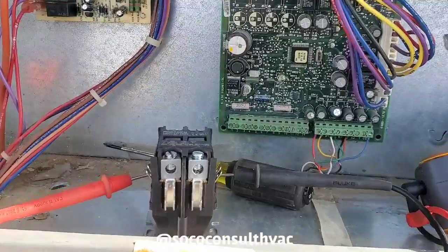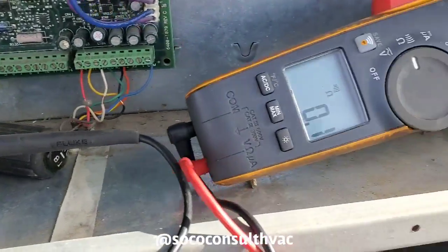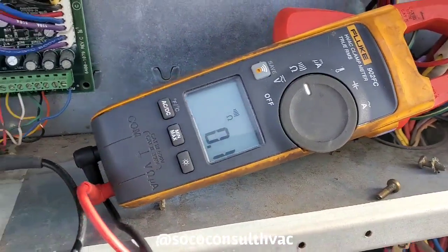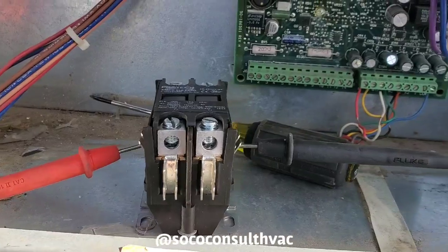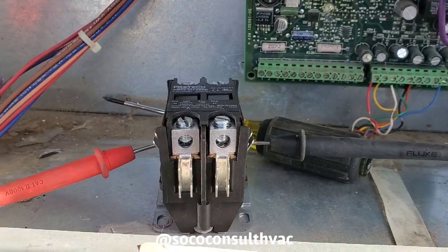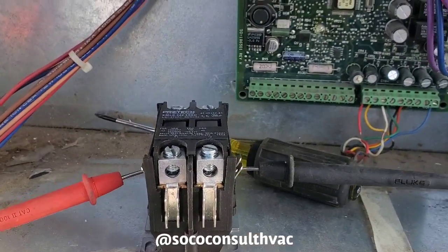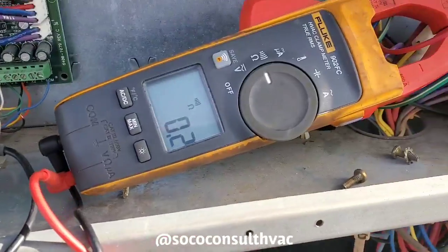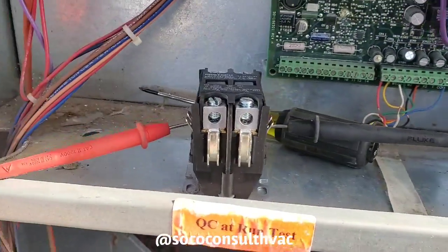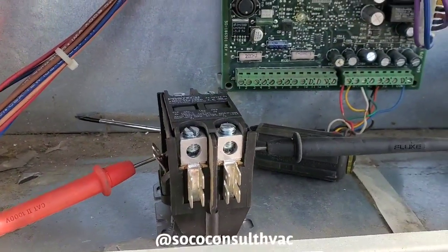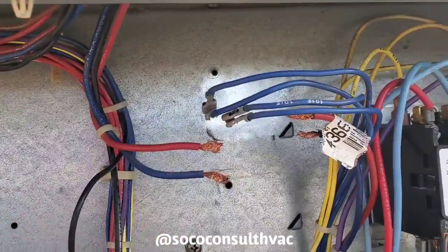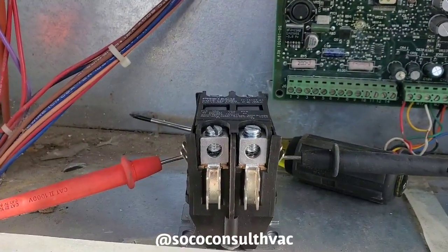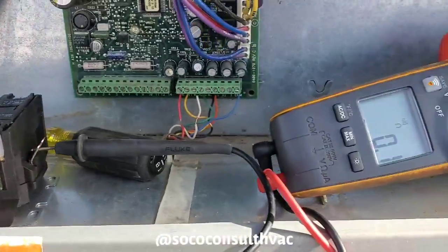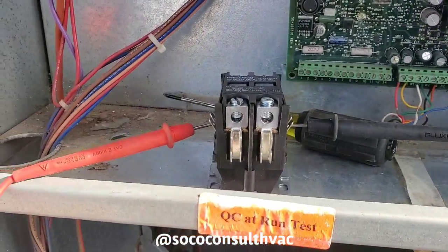All right, we are ohming out our contactor coil, and as you can see, we have 0.1 ohms, which is a dead short across that coil. So that is pretty much the cause of our low voltage issue. It's not necessarily a low voltage short to ground, even though the common is grounded here at the transformer, so it essentially is, but it is a hot to common short in this case. That's also a hot to ground short.